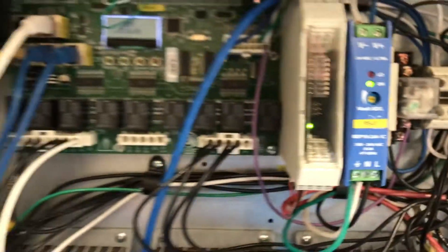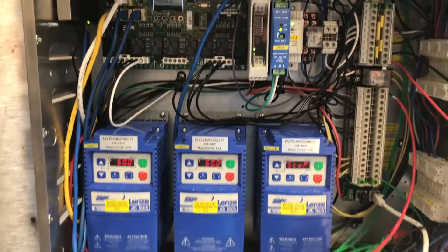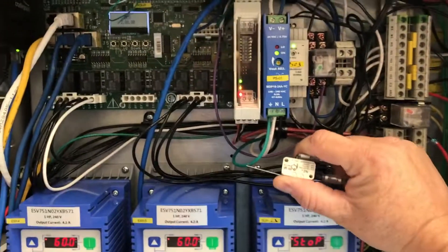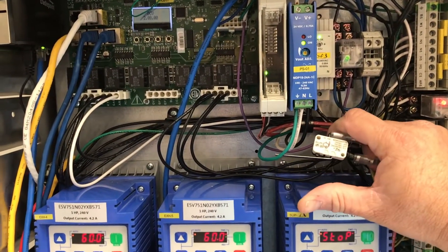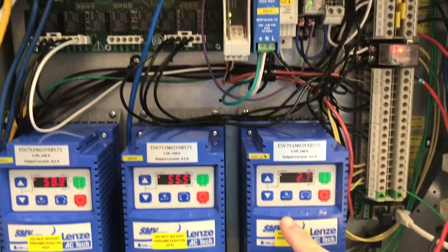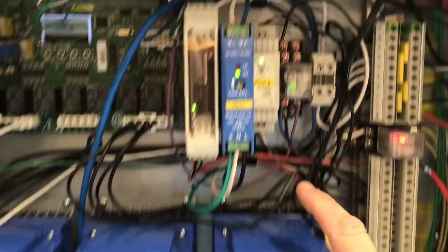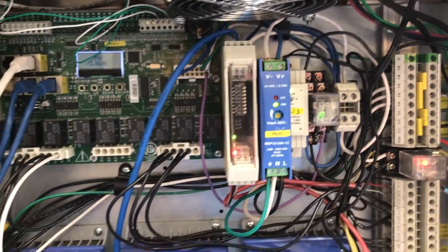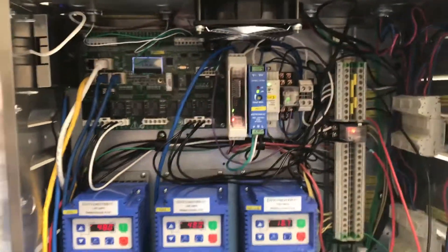The control package will also energize the ST terminal with 120 volts to trip your shunt trip breakers, and if there's an electric gas solenoid, that will be de-energized. Once the Ansul system is reset, the microswitch will go back to its normal position closing C1 to AR1 and the control package will go back to its normal operating condition: lights on, supply on, exhaust on.